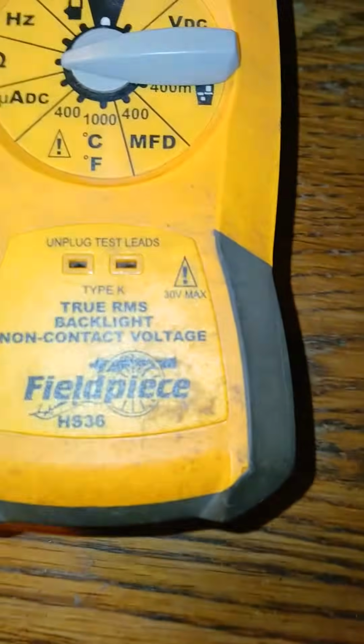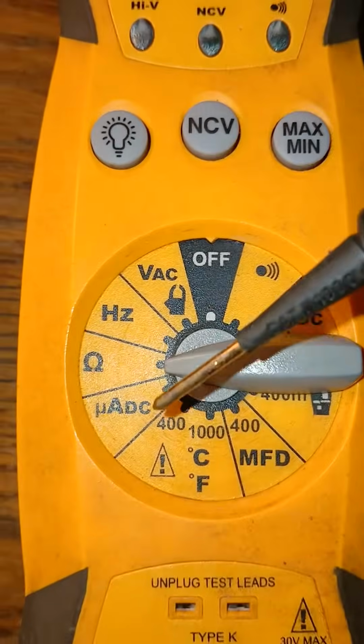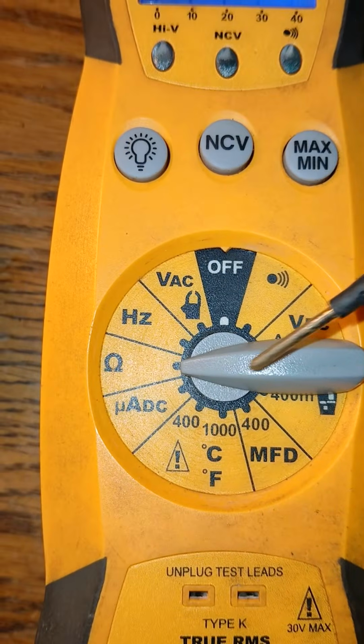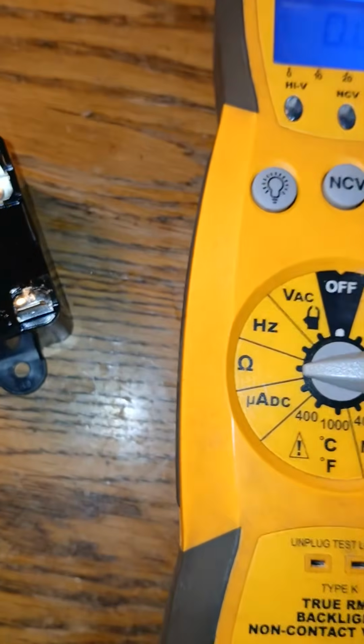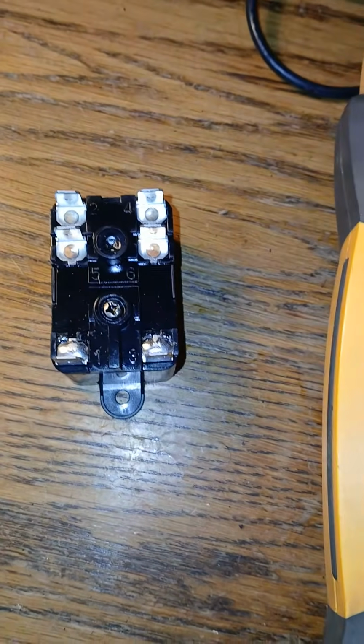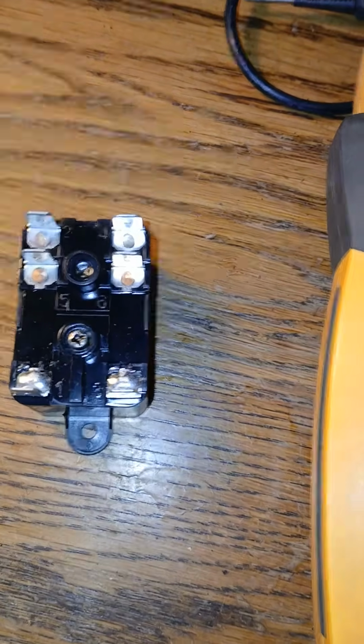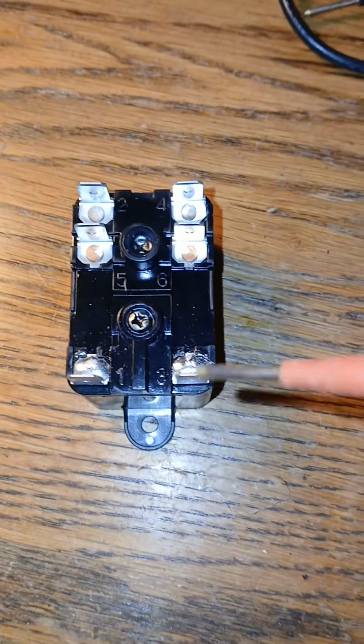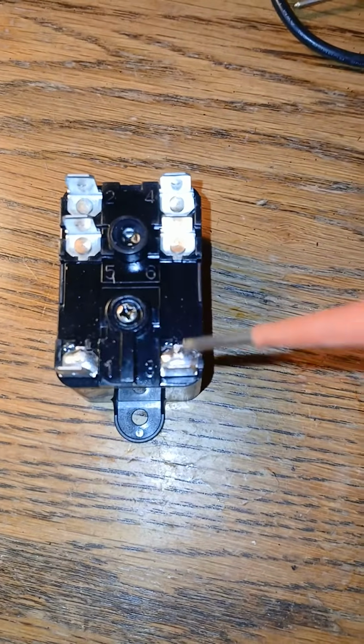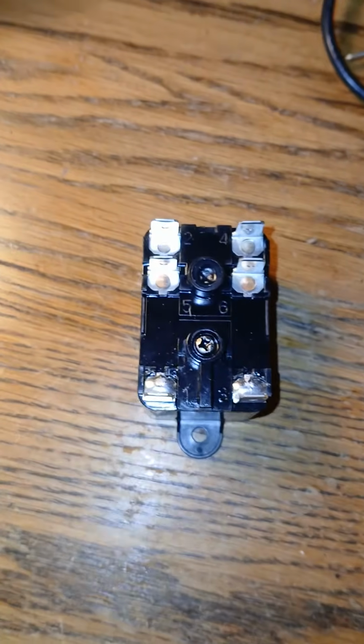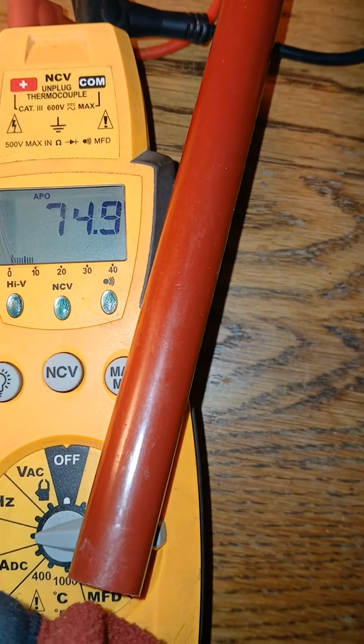So keep in mind, now we are in ohms. So we're reading resistance here in ohms. This is turned this way to the little horseshoe thing. So we address this low voltage coil here. We should be between 70 and 80. We're at 73. Let's get another look here. We're at 74.8, which is in the range of 70 to 80, which is good.